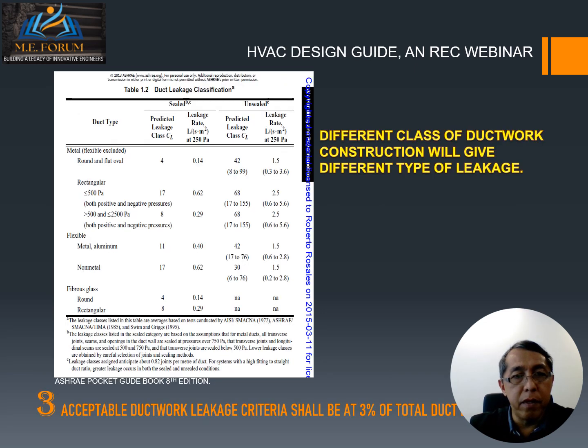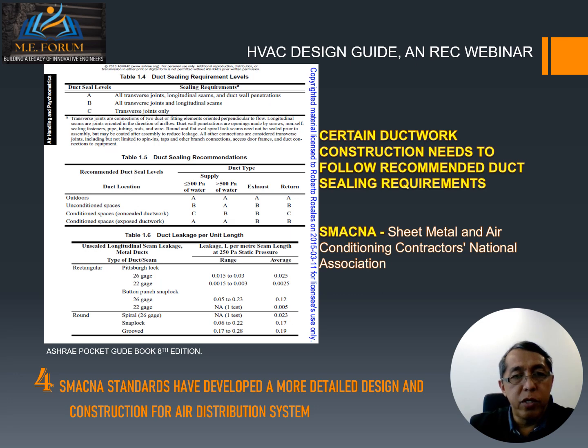Number 3, acceptable ductwork leakage criteria shall be at 3% of total duct length. Different classes of ductwork construction will give different types of leakage. Number 4, SMACNA standards have developed a more detailed design and construction for air distribution system.